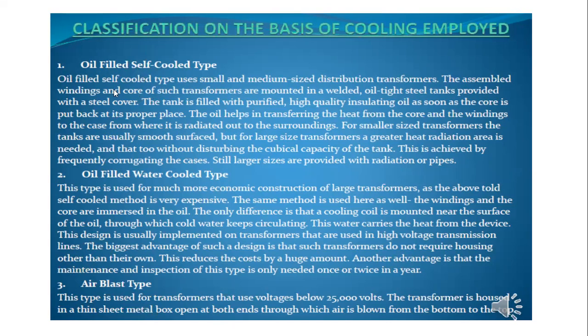By using this oil-filled self-cooled type, we are increasing the cooling for the transformer, and this will be used only for the medium and low voltage distribution transformers. In that case, we are using a tank filled with purified, high quality insulating oil. This oil helps transfer the heat from the core and the windings to the case.